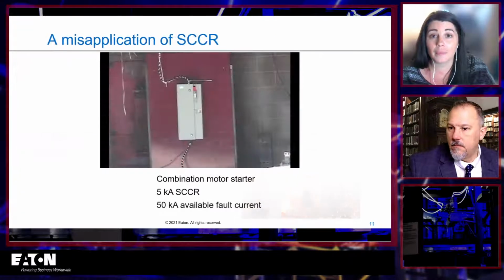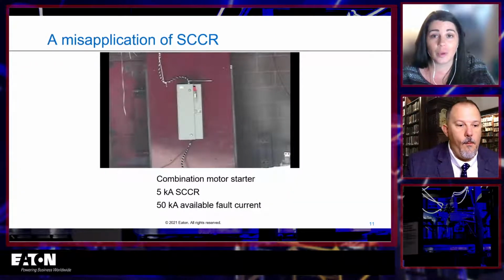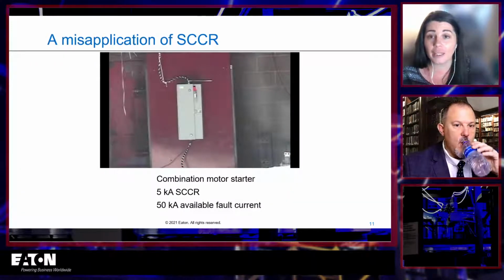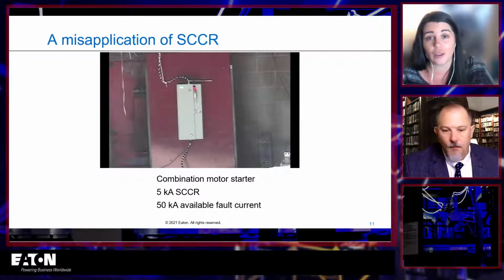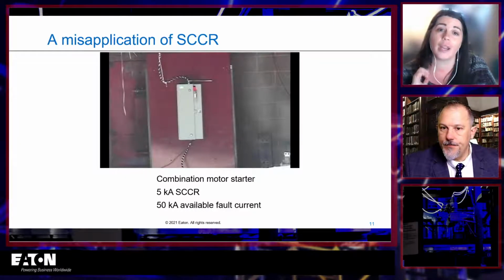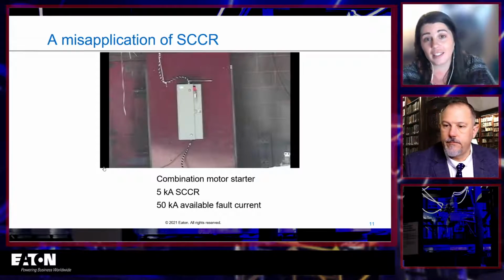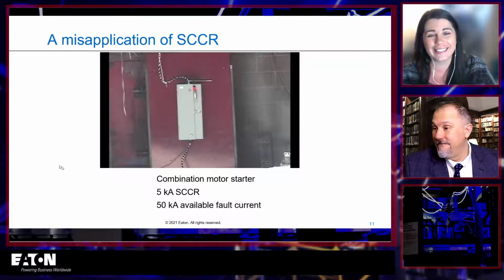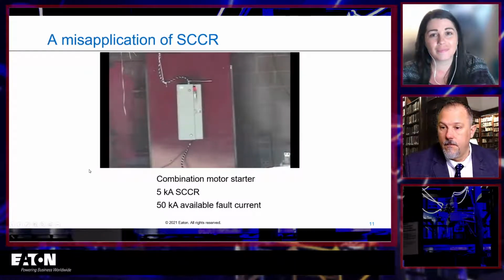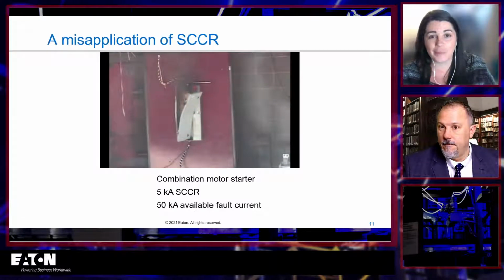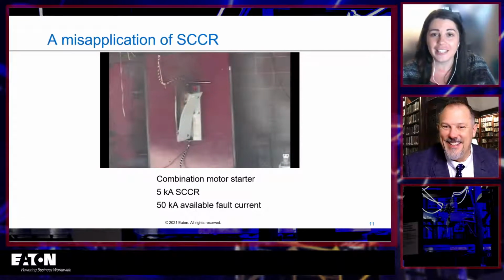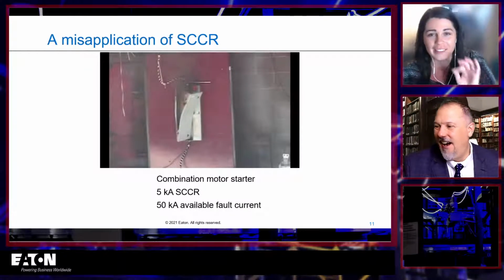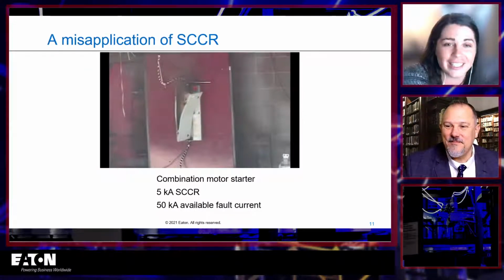Good discussion. So here, once again, a misapplication of short circuit current rating. This is a combination motor starter. This is at 480 volts as well. 5 kA SCCR, 50 kA available. Play that video. 3, 2, 1, 0. I love the uh-oh at the end. That's just the perfect amount of concern, right?